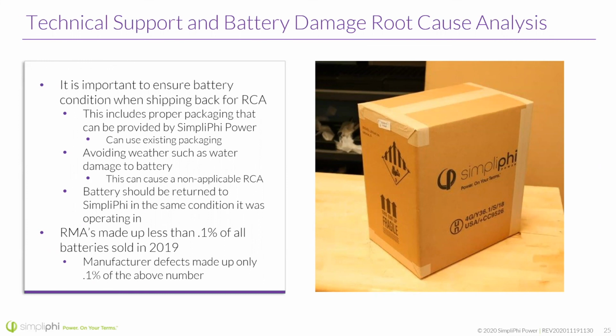RMAs, and actually this number is, I believe, even lower now than that, made up less than 0.1% of all batteries sold in 2019. And of that, manufacturing defects made up only 0.1% of the above number. So most of the RMAs that we ran through were issues with a system design issue. So it's important to keep that in mind. We just want to avoid those. There's not a lot of RMAs in the field compared to batteries sold, but we just want to always keep that in mind.